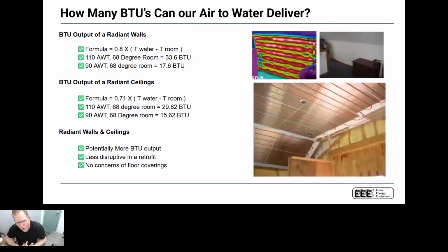When we look at the air to water and sort of understand how many BTUs can I actually deliver into that space, if you look at a 110 degree average water temperature, again, just using a standard radiant wall with a 68 degree room, you can deliver over 30 BTUs per square foot into that room. It's significant. So radiant walls and radiant ceilings aren't that popular, but they are a great way to do it, especially if you're in a retrofit application.